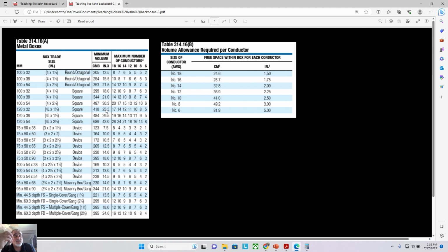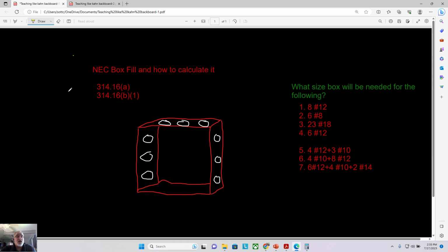Now we're talking about the volume of the conductor, not a cross sectional area. Cross sectional area, you're looking at the end of the conductor, at what this area is on the inside of it in one particular spot of a long conductor. What I'm talking about is the actual conductor itself in volume, an allowance for the whole conductor in there. It's just the wire that comes in, and you basically factor it in cubic inches.